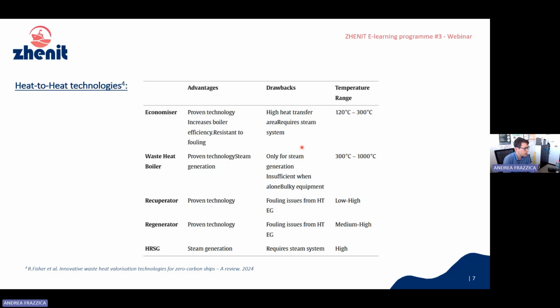Some other technologies are different, in the sense that they directly convert it to another form. For example, using an economizer that can be used for preheating water before generating steam — here you need temperature ranges from 120 up to 300. You can also directly convert the waste heat into steam, generating steam thanks to waste heat boilers; in this case you need much higher temperatures, usually coming from the flue gases.